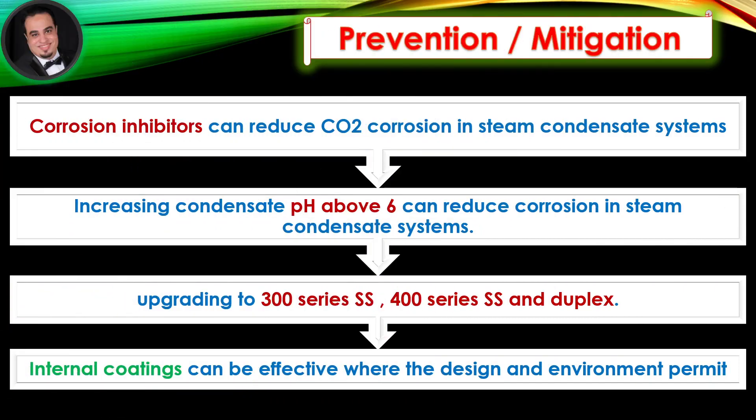Prevention and mitigation: Corrosion inhibitors can reduce CO2 corrosion in steam condensate systems. Increasing condensate pH above 6 is recommended. Upgrading to 300 series, 400 series, and duplex stainless steel is effective. Internal coatings can be effective where the design and environment permit.